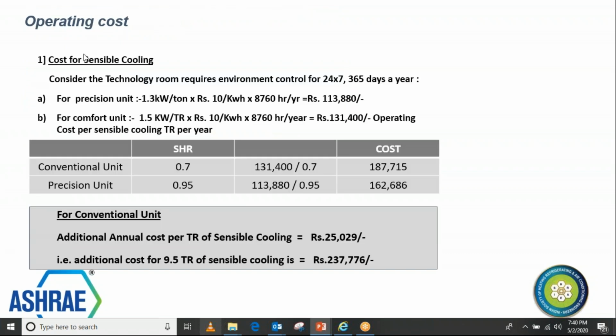For the operating cost analysis, you can see that for 24 hours, 365 days operation, per TR the consumption is 1.3 kilowatt for precision AC, and 10 rupees is the charge per unit, with 8760 hours, and this is the cost coming. Then for the comfort unit, likewise 1.5, 10 and 8760, it comes to 131,400. This is the difference. Then on the SHR for the conventional unit, due to 0.7, this is the cost involved for the capacity, and this is the difference involved. So for 9.5 TR sensible cooling, if you multiply this by 9.5, this is the figure coming to. This is because of the sensible cooling difference, because the sensible heat ratio for conventional is 0.7.